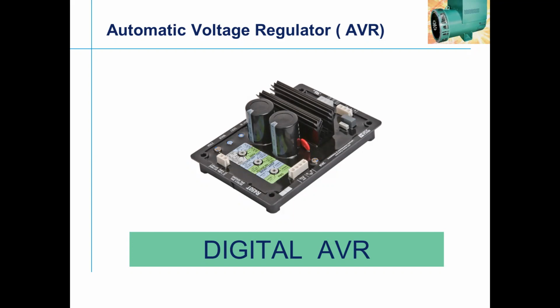Today, we want to control everything sitting from one place. And thanks to this digital AVR, sitting from here, you can control the generators in Turkey or in America or wherever, we can control the system. And people are getting expertise in the digital AVR in India also. And this is quite a proven design. And this also gives some more protection to the generator. Predominantly in analog AVRs, the protections were done more by the panel manufacturer or the OEM, which is going to supply the generator sets. But thanks to the digital technology, we have brought all the protections into the digital AVR.